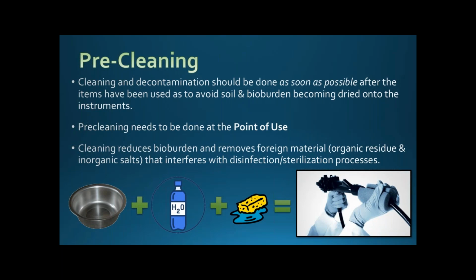With your scopes, in this picture, you have the sponge that you can use to wipe down the exterior of it. You should also have some enzymatic that you can flush through the lumens at point of use into your bag so that you can make sure that you're not only flushing and cleaning the outside, but also getting the inside of those lumens.